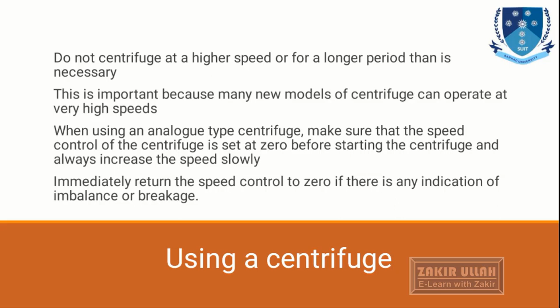If there is any indication of breakage or imbalance, or any sound that comes from the centrifuge, we have to immediately stop our centrifugation and return the speed control to 0 during the usage of analog type of centrifuges.